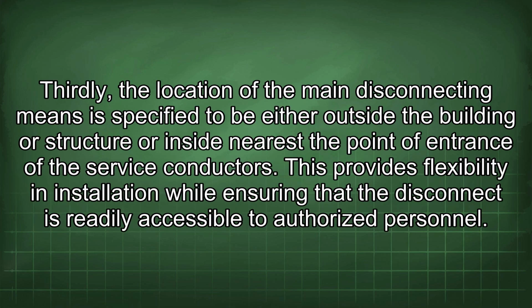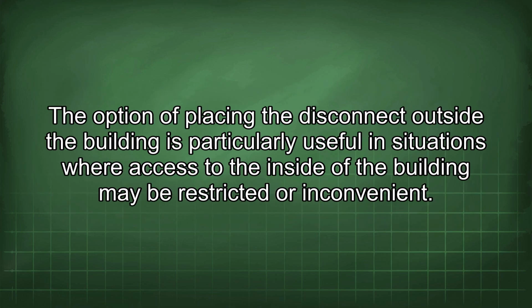Thirdly, the location of the main disconnecting means is specified to be either outside the building or structure or inside nearest the point of entrance of the service conductors. This provides flexibility in installation while ensuring that the disconnect is readily accessible to authorized personnel. The option of placing the disconnect outside the building is particularly useful in situations where access to the inside of the building may be restricted or inconvenient.